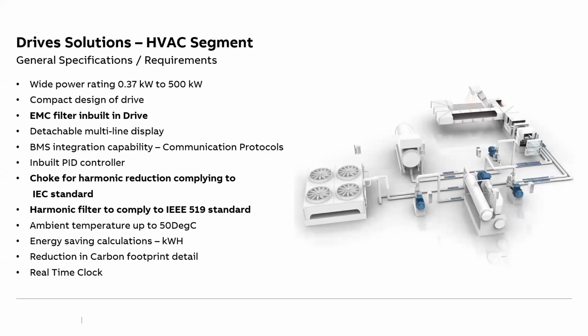Then BMS integration capability. Again, this is an important feature. Basically, this is about the communication protocols. The VFD should have the basic communication protocols inbuilt so that it can communicate with the BMS system. Modbus is the most common protocol used in the industry. Apart from that, there are other protocols like BACnet, Metasys, and others also. So depending on the protocol the BMS is using, the VFD should have those protocols inbuilt.